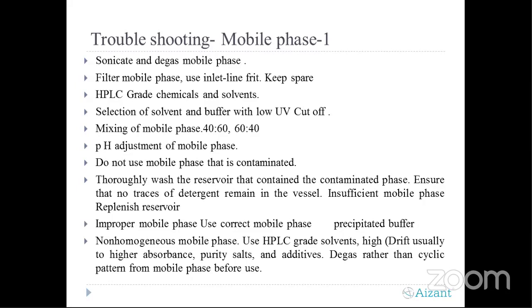Why am I specifically telling you this? Because in the lab, AR grade solvents and chemicals are also available, and by mistake of the chemist, or because no particular standard operating procedure is defined, they can use a substandard grade of chemicals, and that can lead to a number of challenges. What sort of solvent do we have to use? In each solvent you'll find a UV cutoff value provided. What is UV cutoff? It's the specific wavelength below which there is a lot of interference.